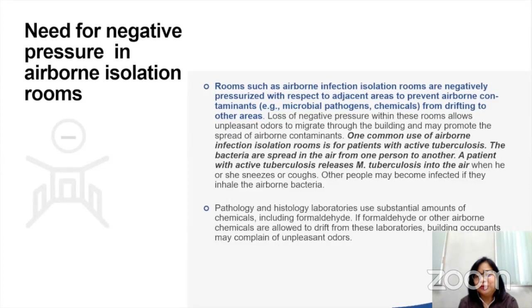Now about operating room ventilation, there is a recommendation that there should be at least 20 air exchanges per hour in the OR. Okay, so how do you do that? You have to reduce the amount of equipment in the OR. And remember, our ORs do not open windows to the external environment. So if you're going to have laminar flow, it may be distorted if you have additional equipment or personnel in the room. What we do is we install HEPA filters to remove aerosols and droplets.